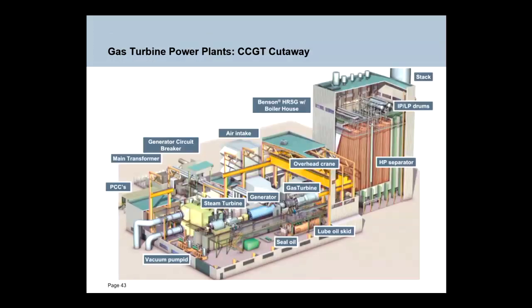Okay, and then here a cross-sectional diagrammatic of pretty much the same plant. So here's the HRSG. You can see inside what that looks like. The gas turbine is here exhausting into the HRSG. There's a generator in between the two machines, and then the steam turbine is located here. It's driving the other end of the generator and exhausting into a condenser at the end of the steam turbine. So this is quite a compact 400 megawatts size unit.